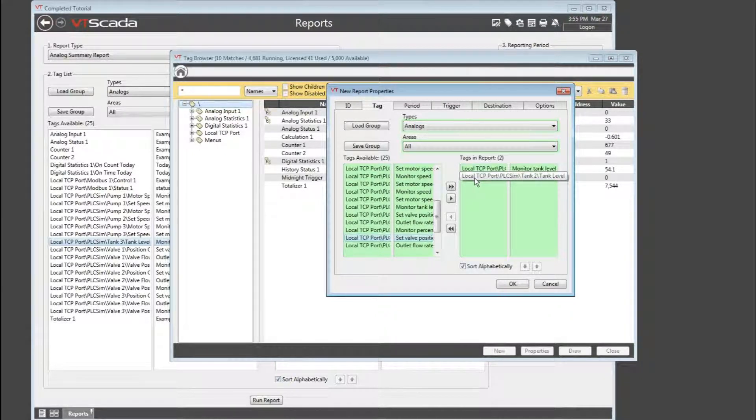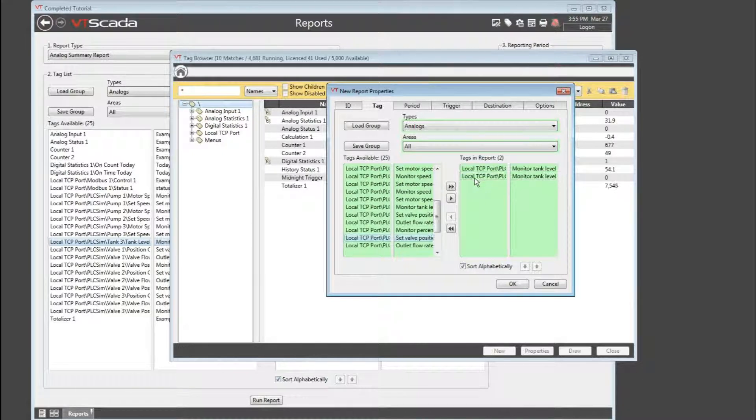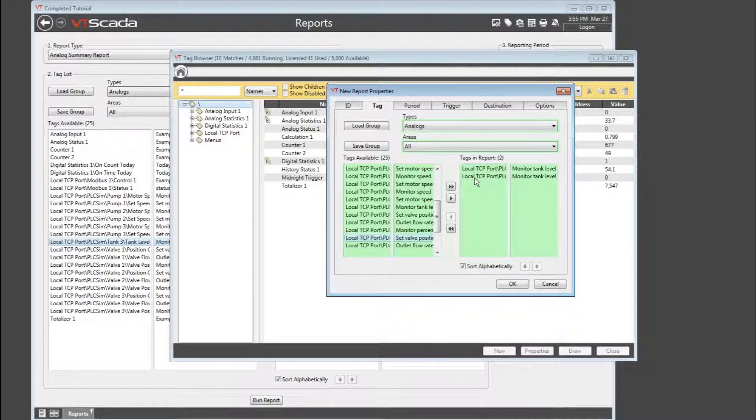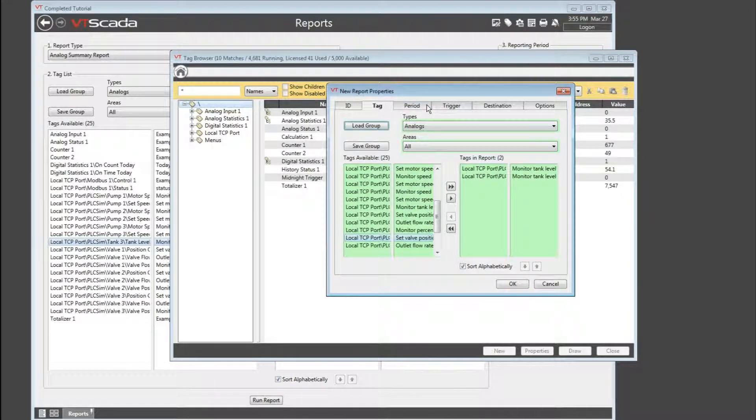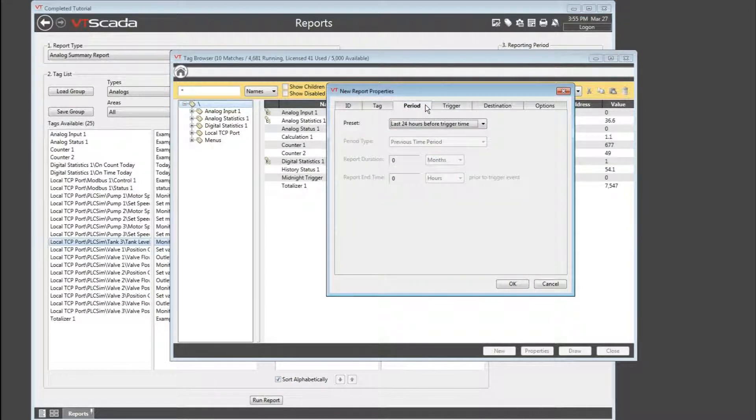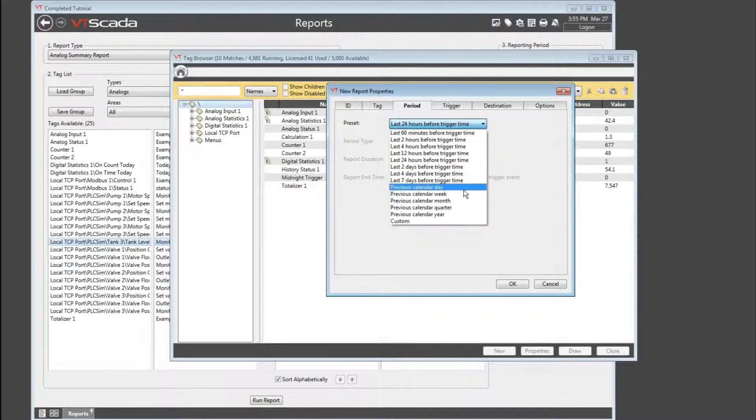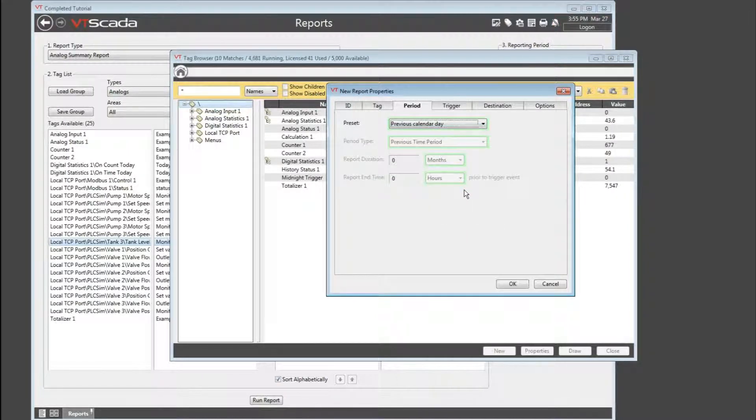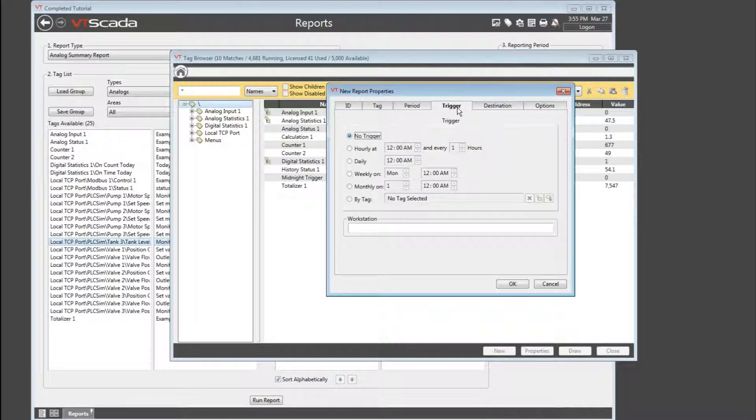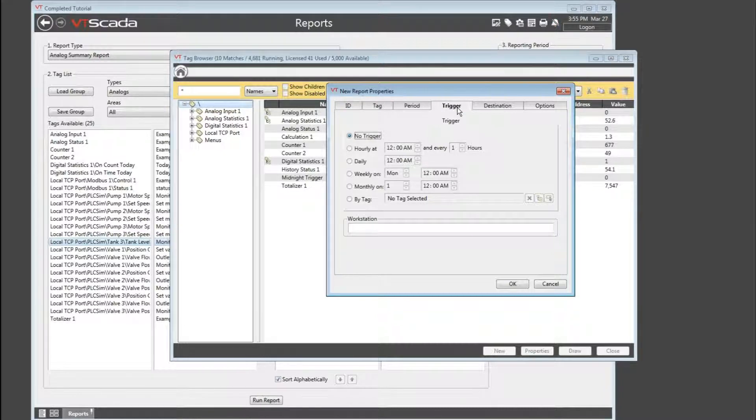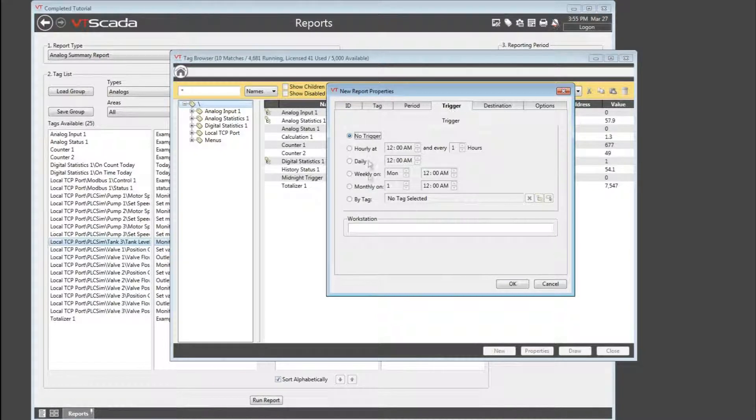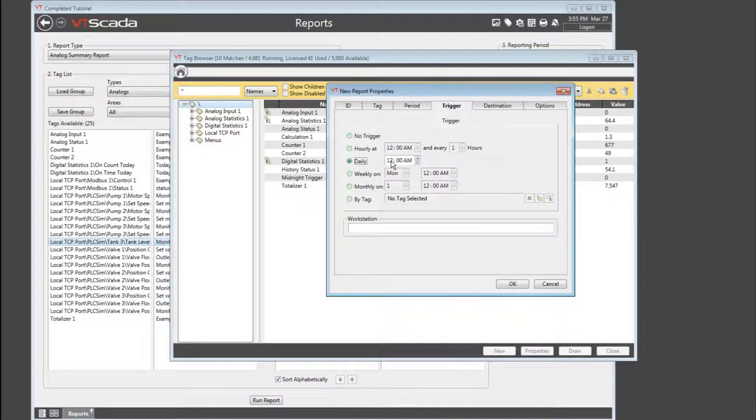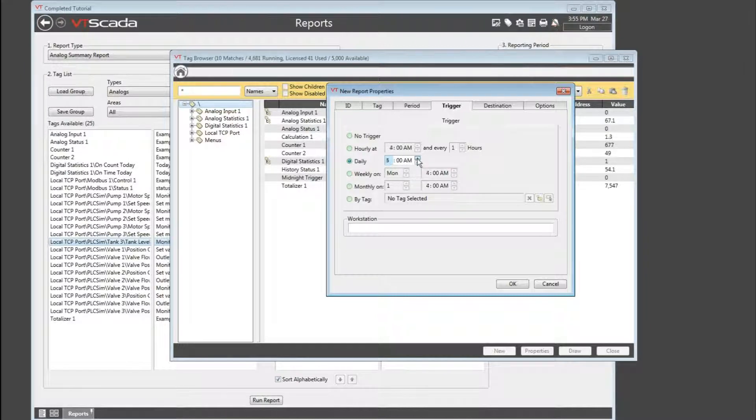You also get to choose and re-sort the order of the tags. By the way, that was true back in the reports page as well. The order of the tags in the list is the same order it will use in the report. Moving on to the time period, I can set my preset time of whichever time period I'd like. I could also have this triggered according to an event. So perhaps you could have your report run when an alarm is used as the triggering tag, or I could make this report run every single day at 8am.